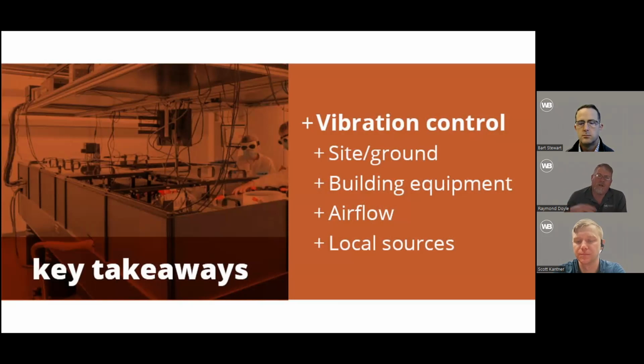And then inside the building, we talk about building equipment. This isn't just the equipment inside the lab that Scott went through in detail. It's really about the vibration created by the HVAC equipment or power equipment that supports that lab. Most people don't understand that when you hear a transformer hum, there's vibration generated by that transformer as it transforms the power. We want to make sure those are located somewhere that won't disrupt the science inside the space.